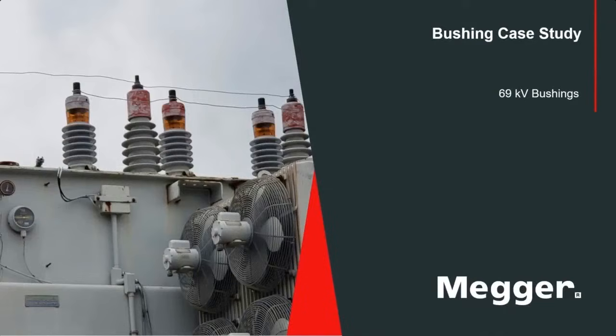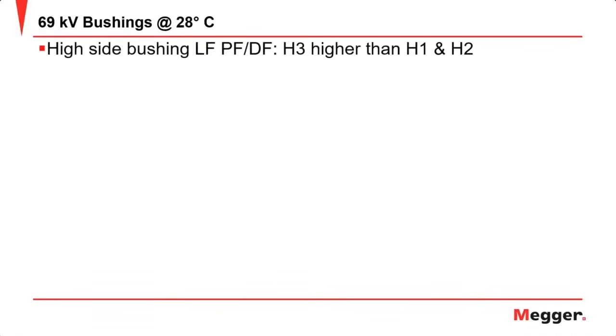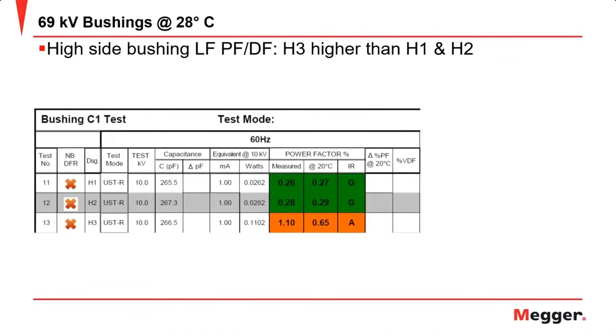So now looking at our next case study for these 69 kV bushings. This customer was performing some routine maintenance on a transformer, and what they saw is that 2 out of the 3 bushings were looking good, and they had 1 that was aged. And aged with the ITC correction, 0.65. Is it a little high? Yes. But is it something that would jump out and scream investigate? You can tell me. You're the ones who have been in the field more than me. But I think in talking with customers, if this was all the information that they had to go on, they might have said, well, yes, it's changed, but it might be in good enough condition to put it back into service.